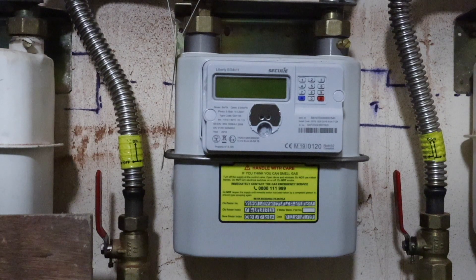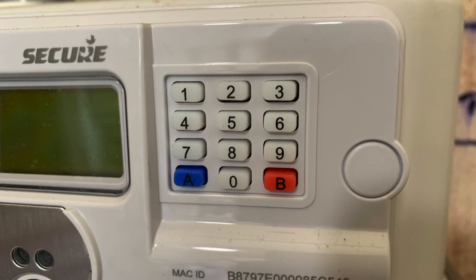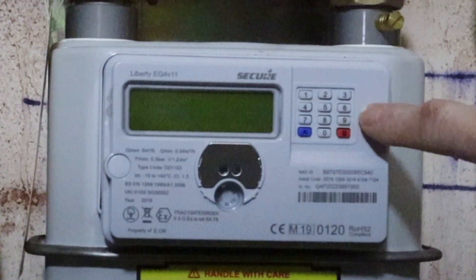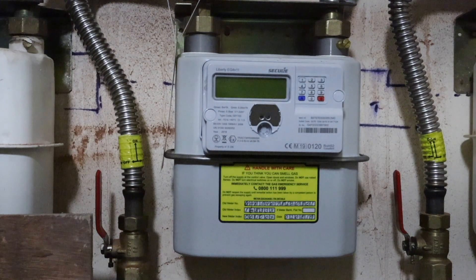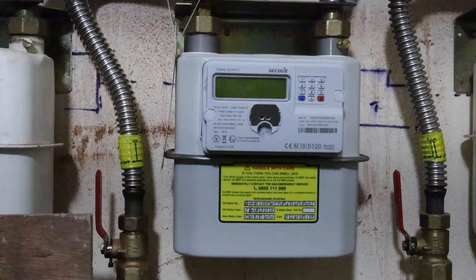The next gas meter we're going to be looking at is this Liberty EG4v11 smart meter. The slight difference from the last one is we're going to be using this keypad, and the main thing we're going to be using is number 9 on the keypad. First thing we're going to do is press number 9 to wake up the smart meter, then press it again until it scrolls through to our volume. We're going to need the volume test on this meter; once we've got to the volume test, for two seconds the meter will display our reading.